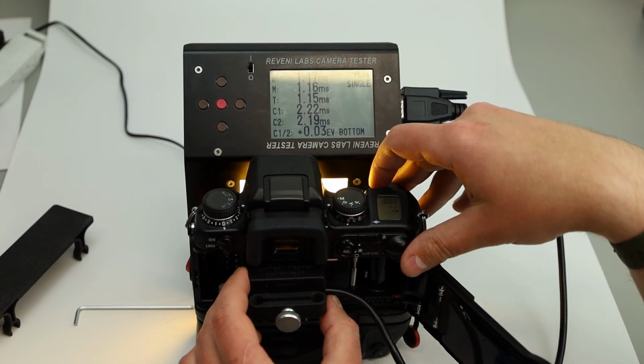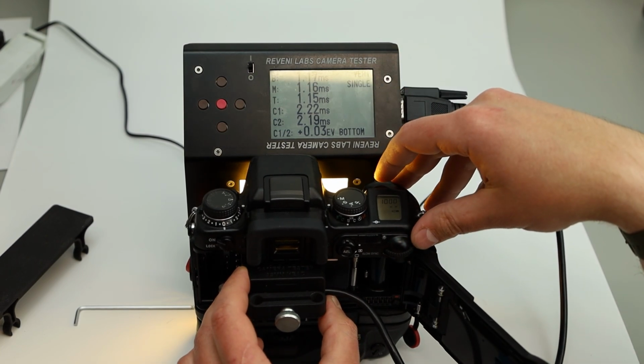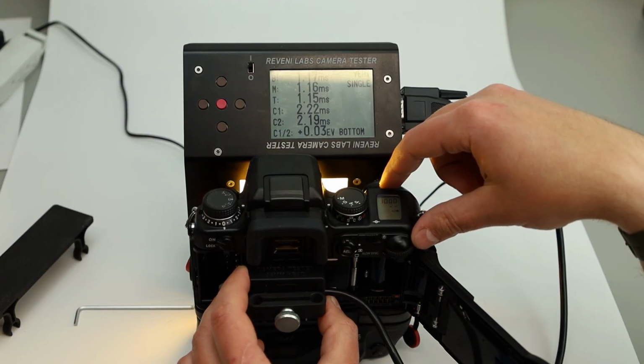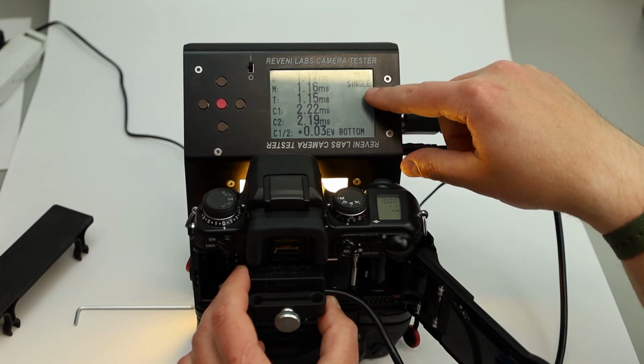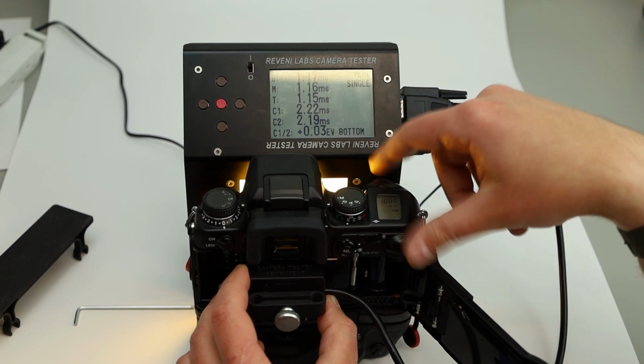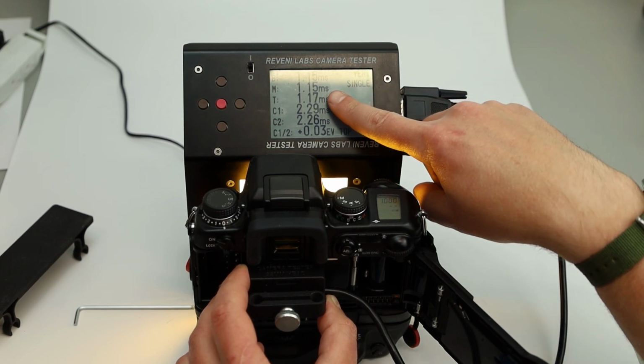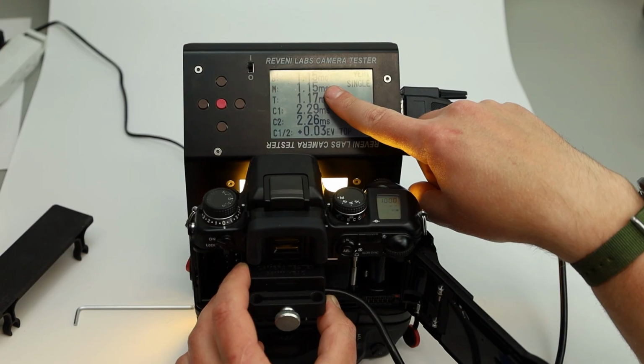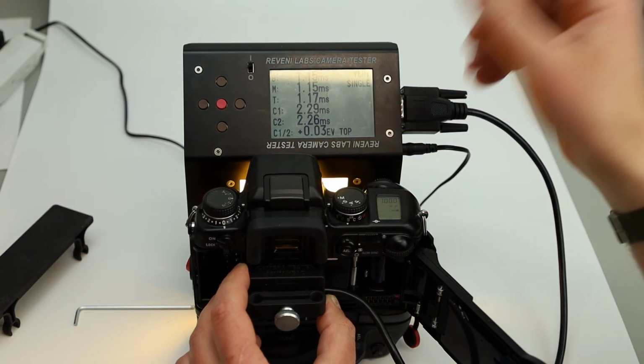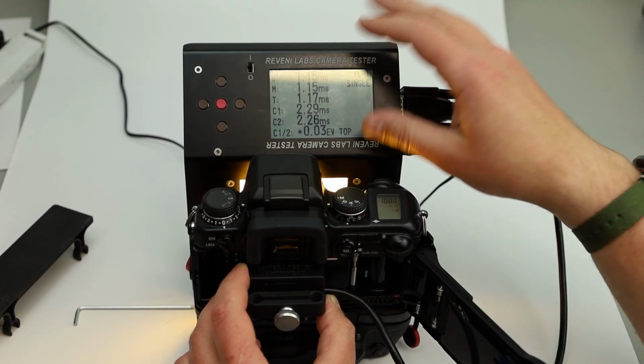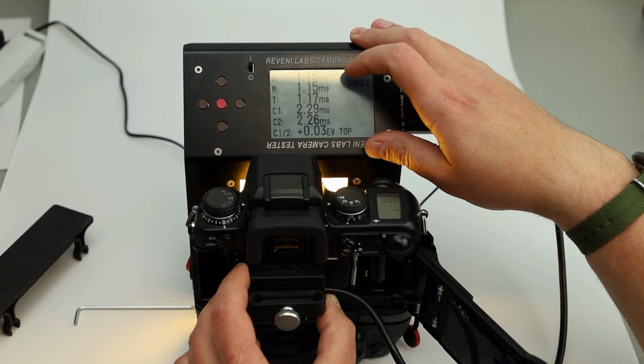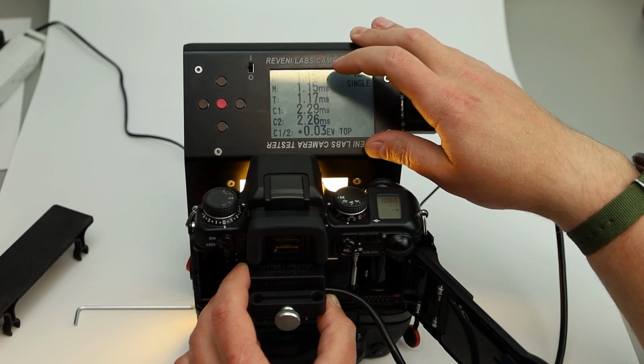The next step is to determine the offset. So if I'm using this camera as a reference camera and I'm saying that this camera has a good 1/1000th speed, the tester is reading 1.15 milliseconds at the middle. That's telling me I need to set an offset of negative 0.15 in the calibration menu to bring it to 1.00 milliseconds.